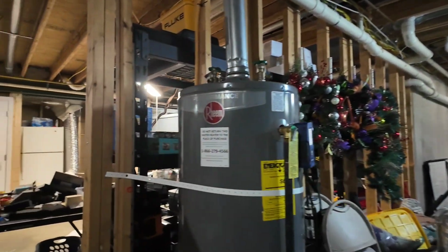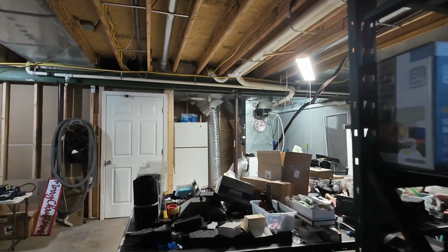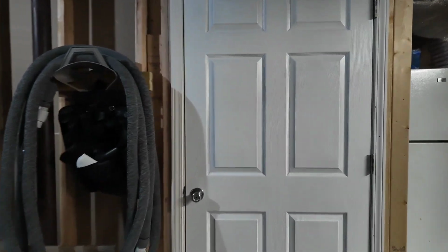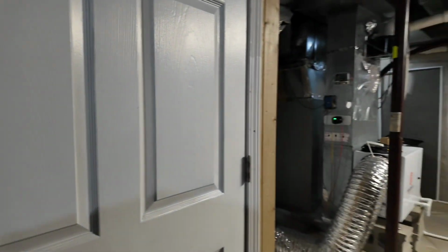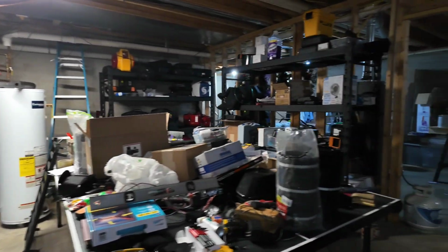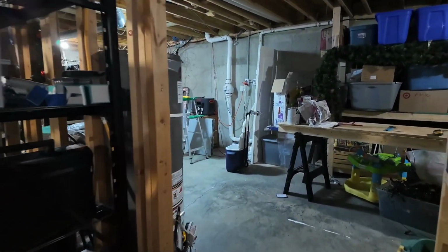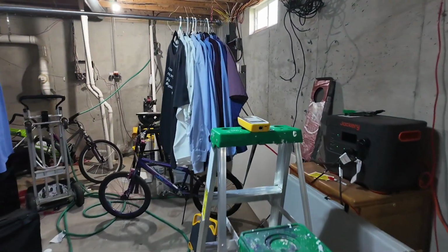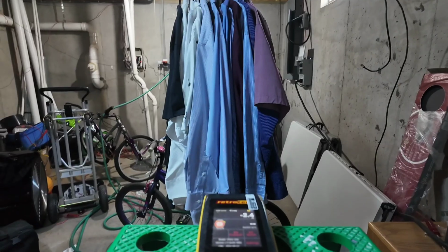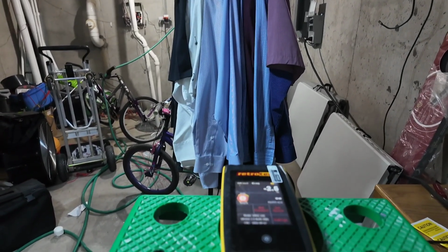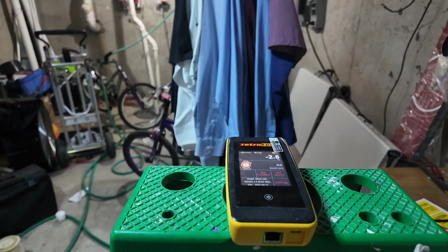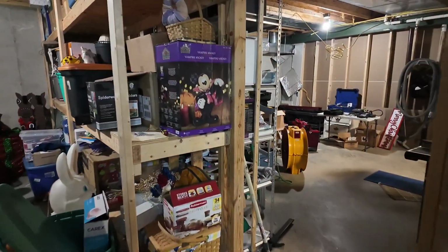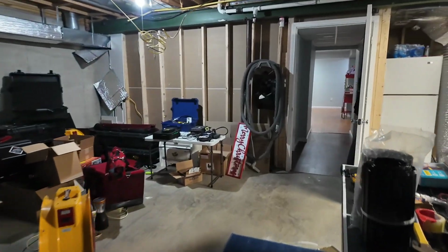Now it says open interior doors directly leading to the CAS. Measure and record the pressure in the CAS with reference to outdoors. So we're going to the door, we're opening the door, and we're going back to our manometer and seeing if it made the pressure more negative or less negative. And it actually dropped it down to negative 2.4, negative 2.5, which is not a drastic difference, but it is less negative, so we will close the door.